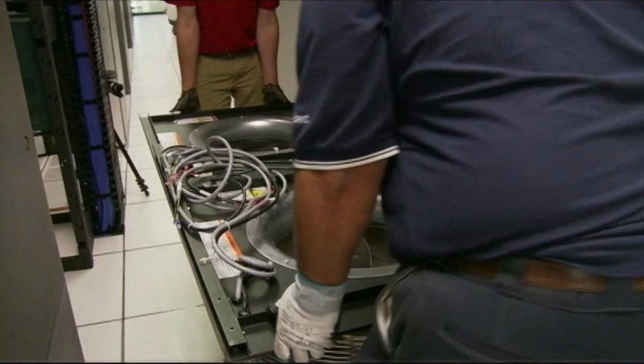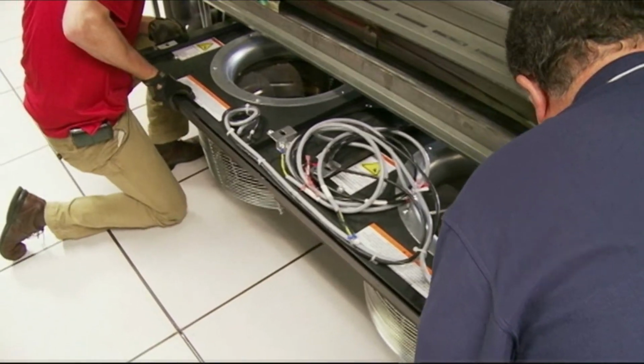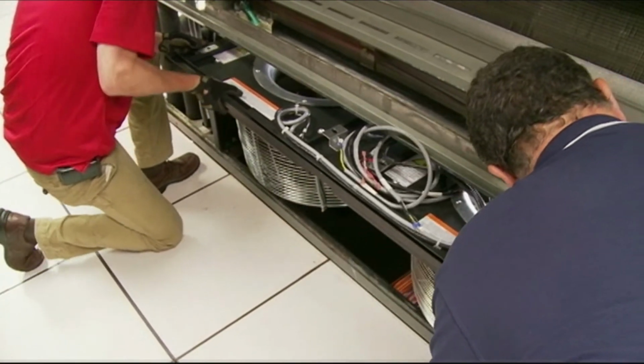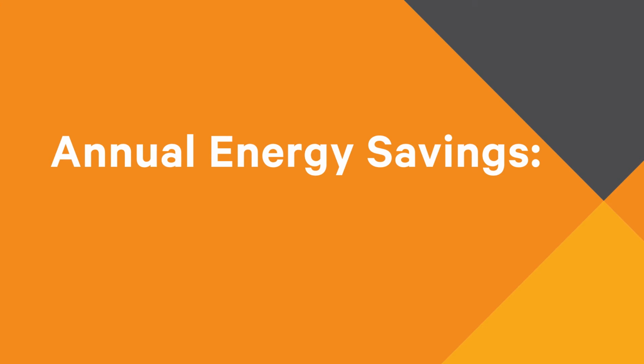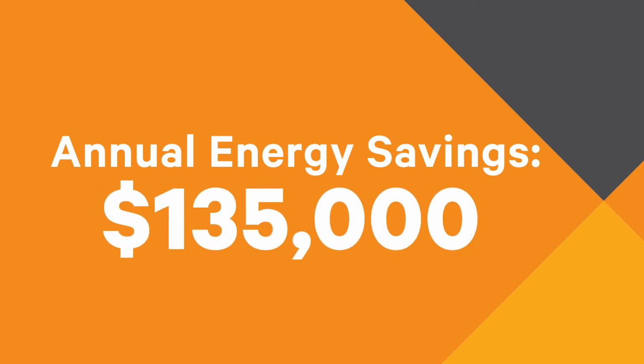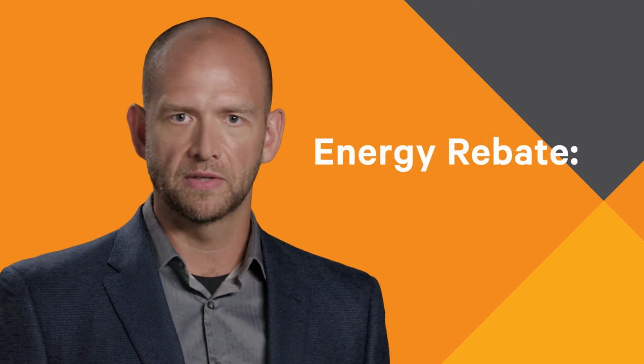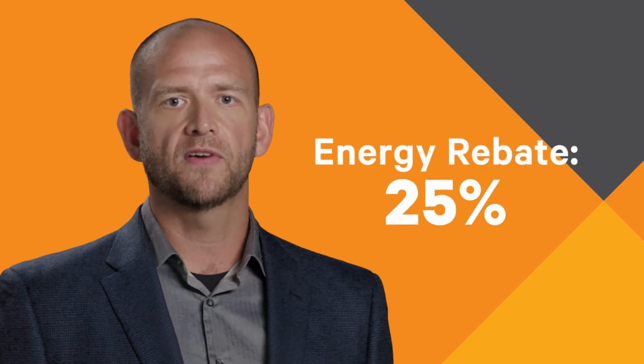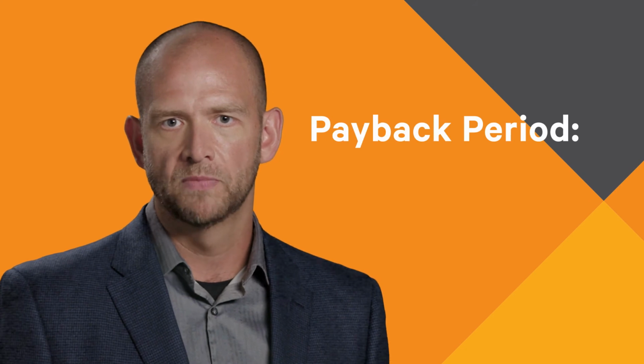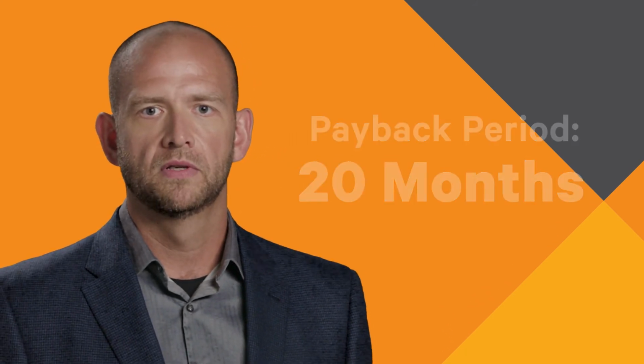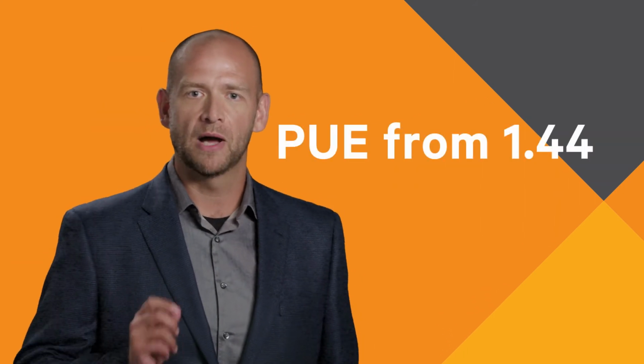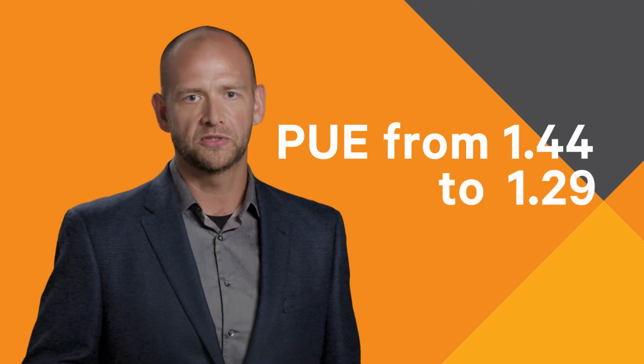Upgrading the units with EC fans, advanced controls, and adding aisle containment to the rack rows could reduce annual cooling system energy costs by about $135,000. Plus, you might qualify for an energy rebate, which would average around 25% of equipment costs. The energy savings and the rebate against the equipment and installation costs will yield a very favorable payback period, only about 20 months. Plus, your PUE will drop from about 1.44 to 1.29.